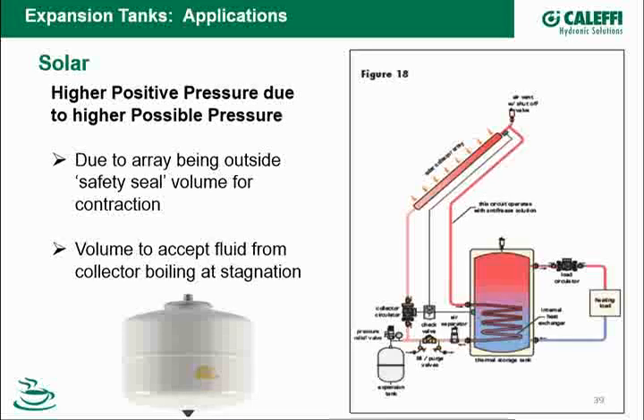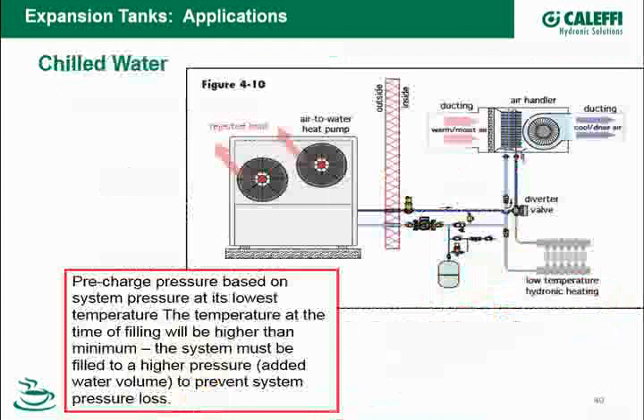Then there's chilled water. Chilled water tanks tend to run a little bit smaller. They don't see the high temperature difference that a hydronic heating system does see. Everything is calculated based on the chilled water temperature as your minimum temperature and the minimum pressure at that point. Now, when we start to fill the system up, the system is probably going to be filled at a higher temperature than the minimum on the system.